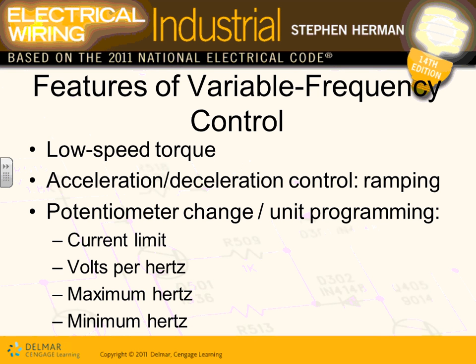AC, single phase, driving a three-phase motor via VFD. Okay, so what do you do? You can change the unit program. You can current limit that. Inrush current, you can limit it. Volts per hertz, maximum and minimum hertz. So you can set your maximum speed for the conveyor, the minimum speed, and your current limit.